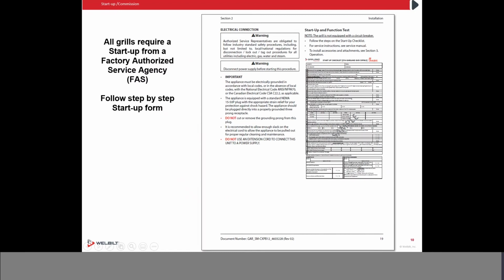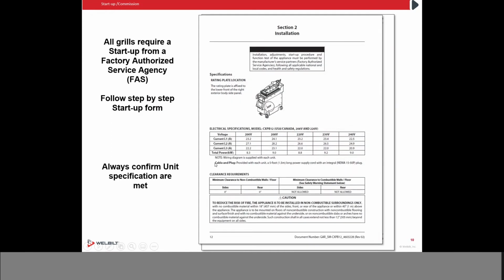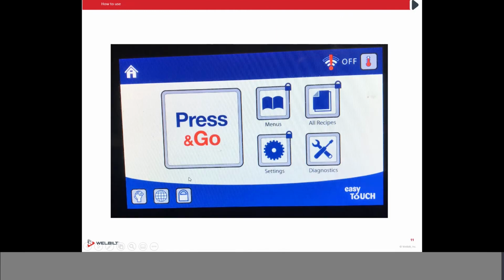Startup forms, again, we know that startup has to be done by a factory authorized service agency. There's a step-by-step form to follow. Make sure we're not pencil whipping the answers. So if it asks what the voltage is, check the voltage. You just don't assume that because the data tag says it's 208, it is 208. Actually check the voltages. Again, the UI is the same as all the other grills, so everything else is pretty much the same.